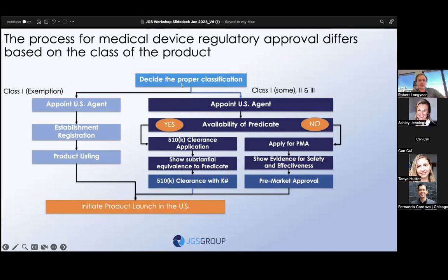Do you need a predicate device when registering class one with the FDA? You will need to pick a product classification for class one, so you still have to go through and look for the classification matching the intended use of your device. If you have a special bandage, you're going to look for the closest fitting category and register under that classification. But it's not technically a predicate device, it's a classification of technologies. Like if you developed a better crutch for people who need to take weight off their legs, you'd go under the class one crutches group that most closely matches your technology.